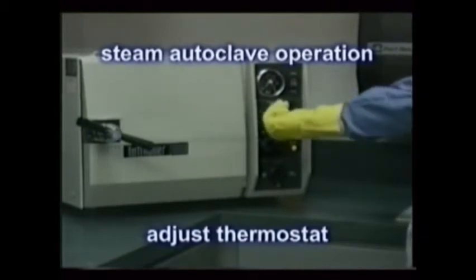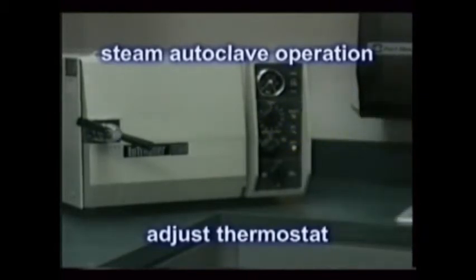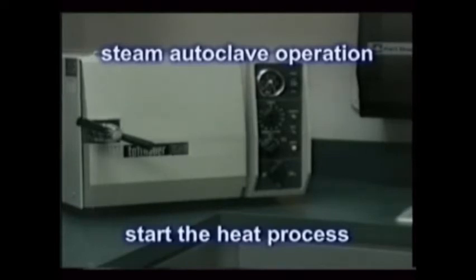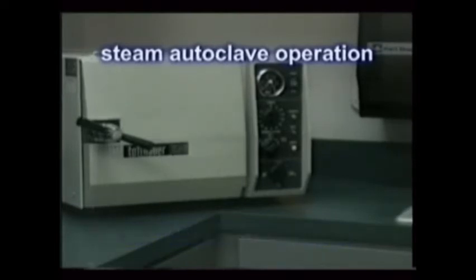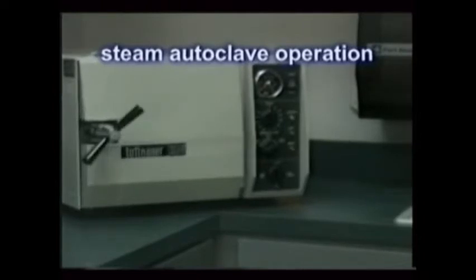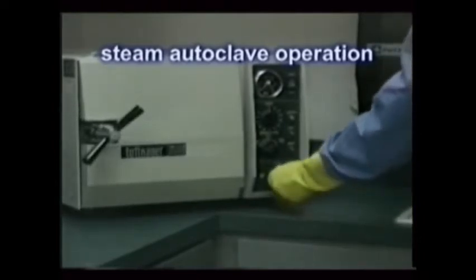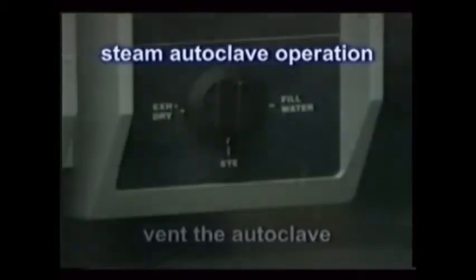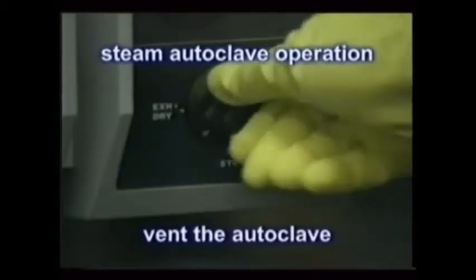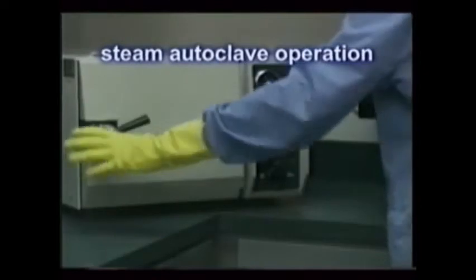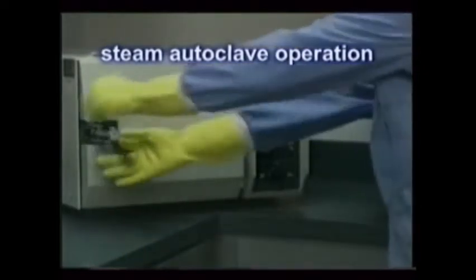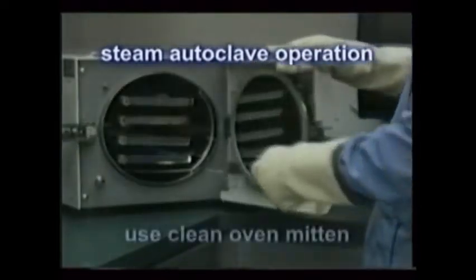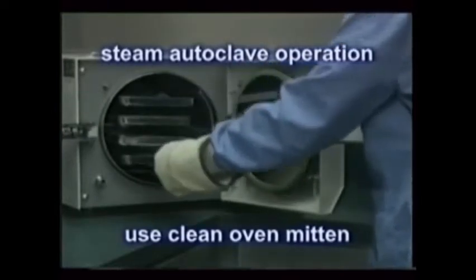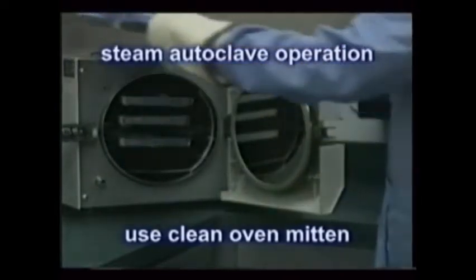Adjust the thermostat to 250 degrees if required. Start the heat process. Only after full pressure and temperature are reached should you start the autoclave's timer. Depending on the machine, it may sound a bell or shut itself off even when the cycle is complete. Then you may vent the autoclave. Slowly open the door only after the pressure gauge reaches 0, and using a clean oven mitten, remove the trays and set them aside to dry and cool off.